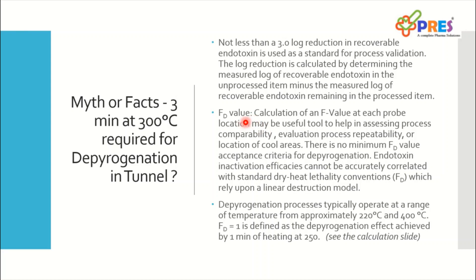FD is not directly connected with endotoxin killing. We can only compare how much FD value we achieve when we demonstrate acceptance criteria. There is no minimum FD value acceptance criteria demonstrated for the depyrogenation process. Endotoxin inactivation efficiencies cannot be accurately correlated with standard dry heat lethality conventions (FD), which rely upon linear destruction. With thermal parameters, you cannot make a direct correlation with endotoxin inactivation — both run in different kinetics.